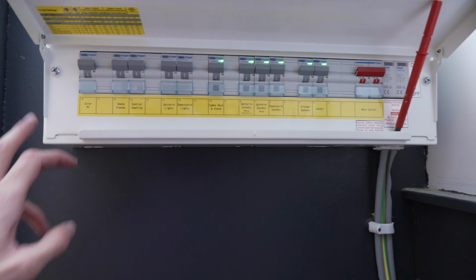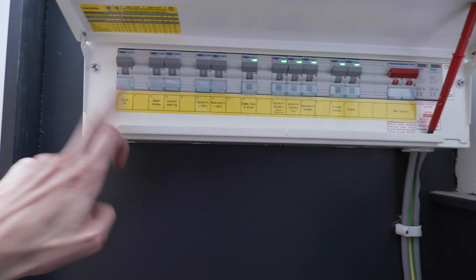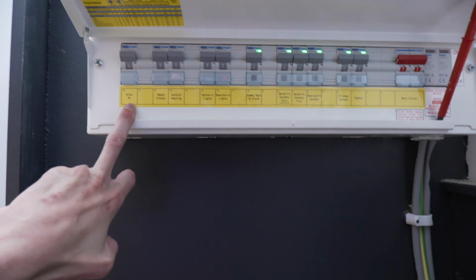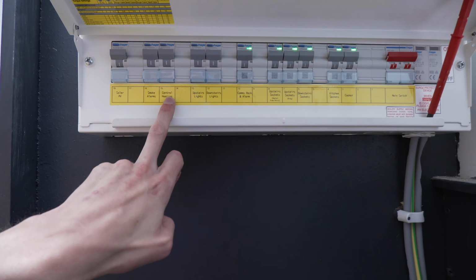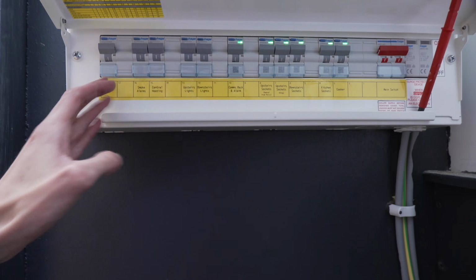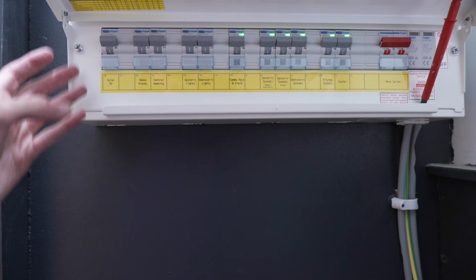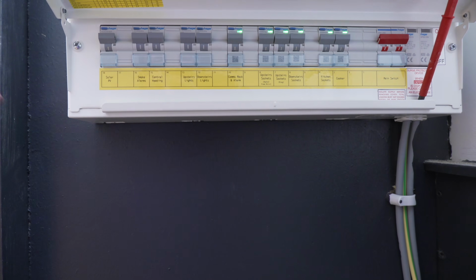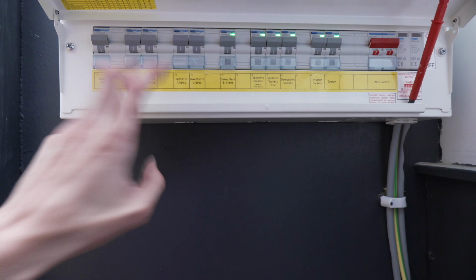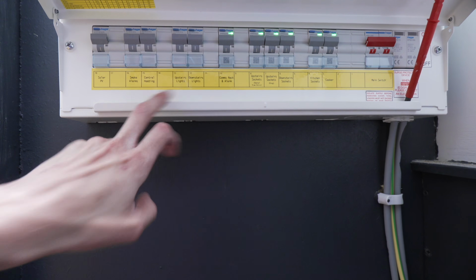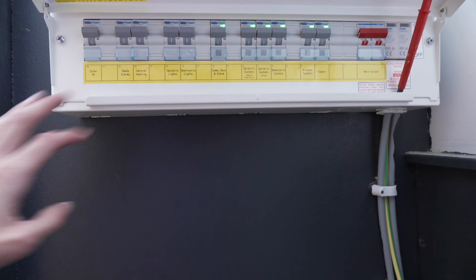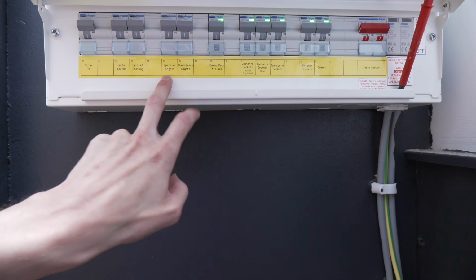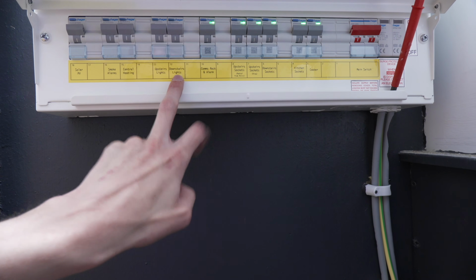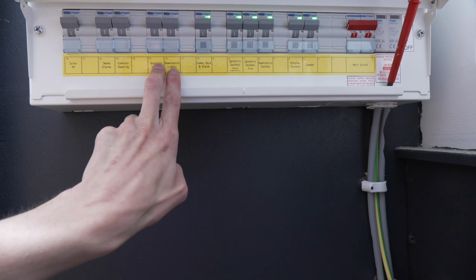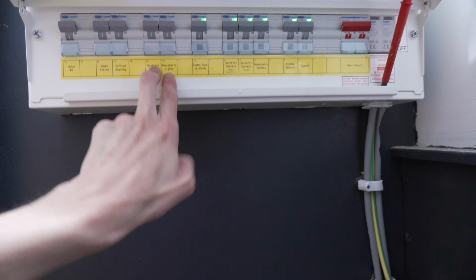So from left to right, we've got solar PV, so that's going to get its own CT to monitor my solar generation. Smoke alarms and central heating, I'm not going to monitor these just because it's such a low draw, it's really not going to be of any significance or worth monitoring. When it says central heating, it's a gas boiler, so all that's really powering is the boiler itself, the pumps and the controls. It's not really powering anything significant. Then we have the upstairs lights and downstairs lights, so we're going to put those through a single CT, so we'll have one CT just monitoring lights.